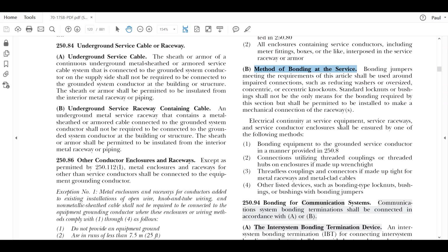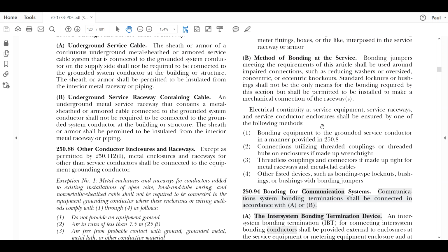So what it says here is, if you have bonding jumpers, they're going to be required if you have to go over impaired connections, reducing washers, oversized, if you screwed up, if you will, concentric or eccentric knockouts. Then you're going to need a bonding jumper. It also reminds us that in that case you're not going to be able to use a standard lock nut or bushing. Now, you can use it for mechanical, meaning holding the raceway in place, but you can't use a standard lock nut for this application.